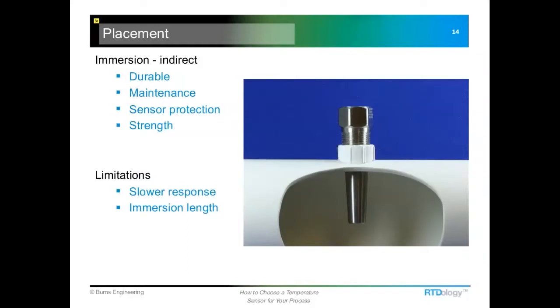Some of the limitations, though: we do get a slower response time. So if you had a process that was changing temperature rapidly, a thermowell like this would probably not be suitable. A typical time constant for this would be around 25 seconds, and that's only for roughly 2/3 of the total temperature change. So if your process is changing temperature, let's say, going up and down every minute, this would be a bad choice. However, in our process here, we don't have that issue. It's just a steady state measurement where we're heating water.